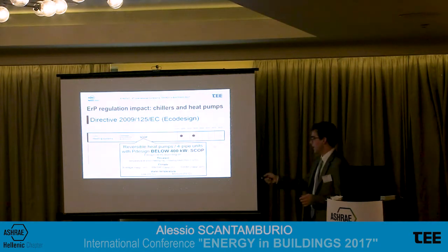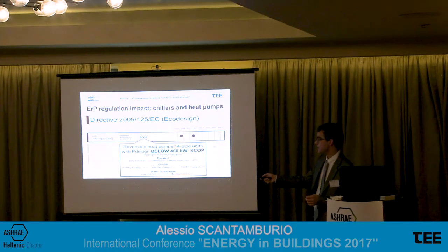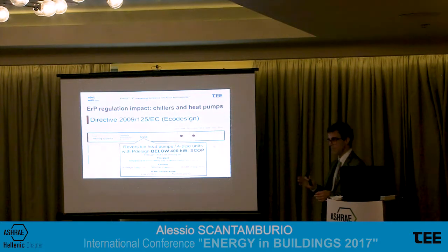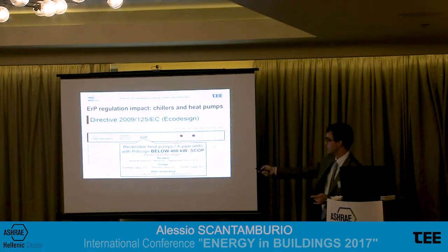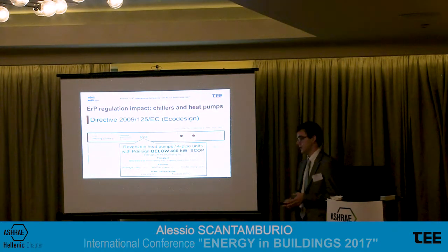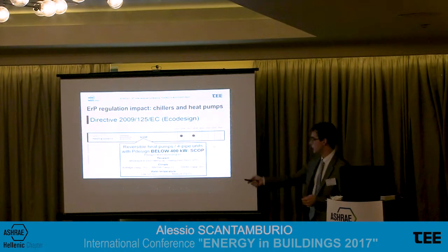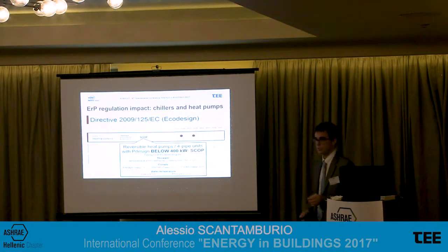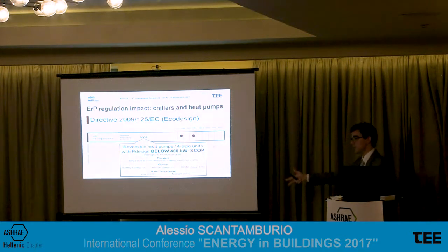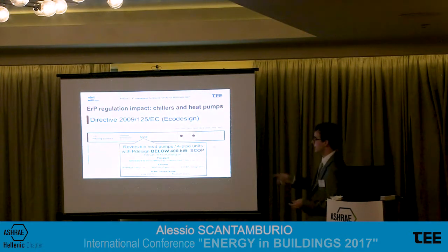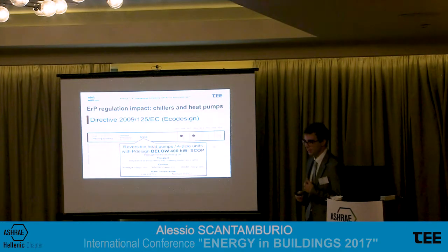okay? Then there are three choices in terms of climate. We have average with a design temperature of -10. We have a warmer climate, design temperature 2 degrees, and colder, -22 degrees. So again, an additional parameter which affects the design power. The last one, of course, probably the most important one, is the water temperature level. We have two possibilities: low temperature 35 degrees, medium temperature 55 degrees. So once we have selected these three parameters, we know the design power of our heat pump.